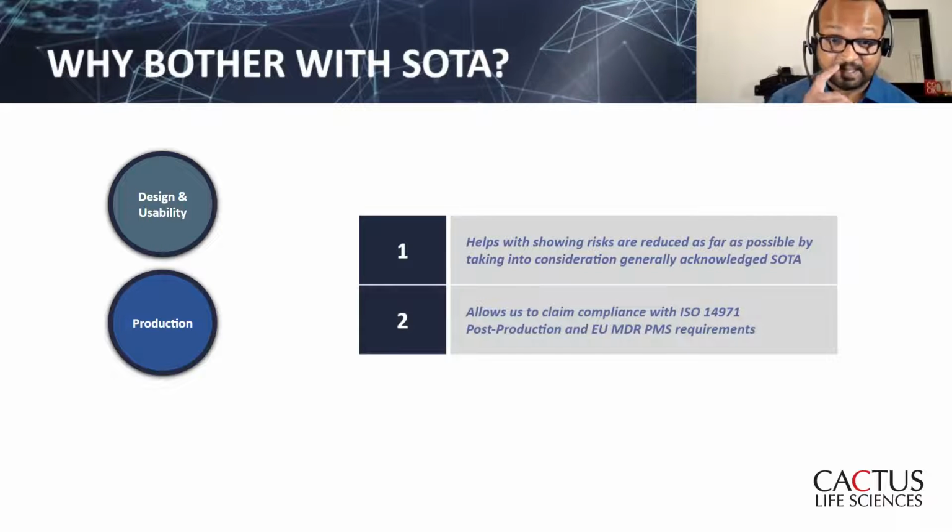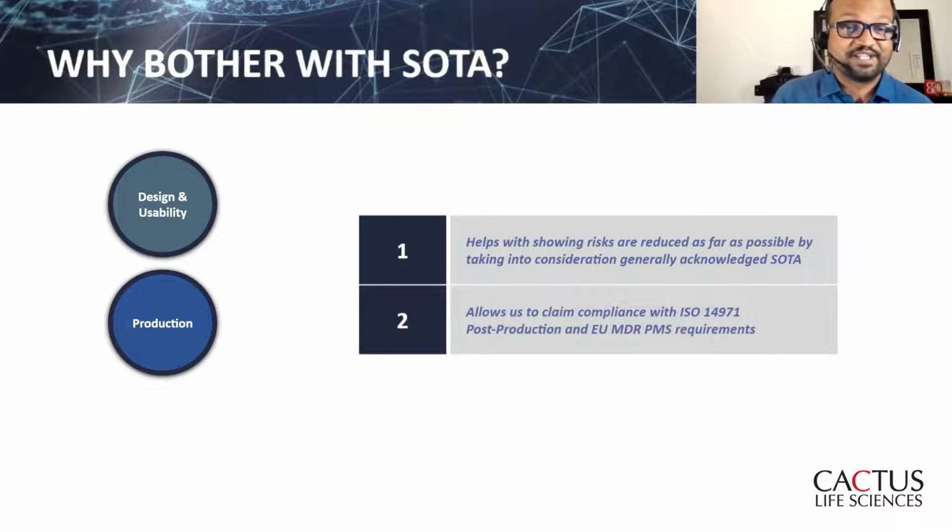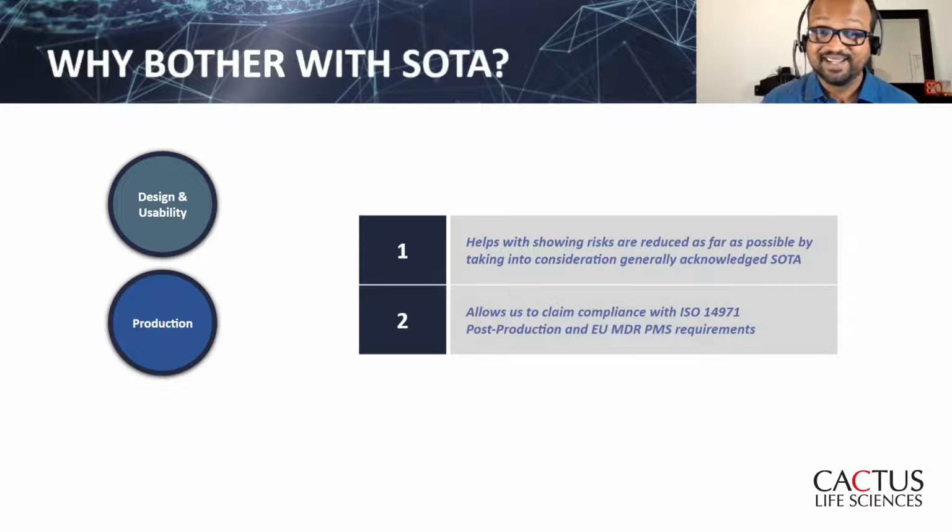Second, and this somewhat follows the first, if we do number one right, we get to claim compliance with a couple of ISO 14971 and EU MDR requirements specific to reviewing similar devices in post-market.